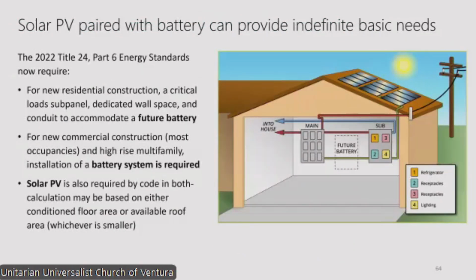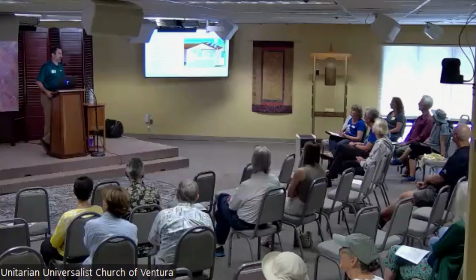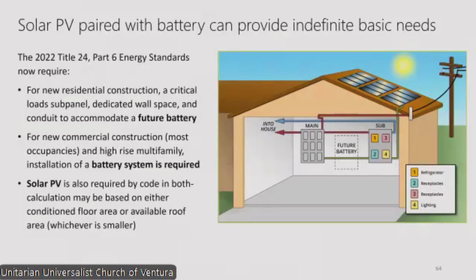PV and battery: codes for new construction are increasingly requiring these. PV is required on new construction, and battery readiness is required, so you have to segregate a critical loads panel in new construction to accommodate a future battery. Non-residential and large multifamily buildings, four stories and above, actually require PV and battery prescriptively. More and more the codes are requiring that, and if you have a properly sized PV and battery system, it can meet your basic needs potentially indefinitely during a protracted outage.